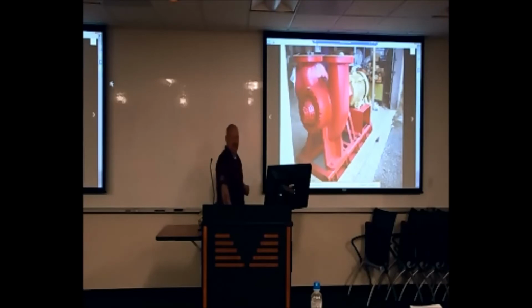You hear that big loud bang, then you know that you've probably got a big air problem in there. I would put a little Hoffman air vent up on the top of this unit, and it'll just automatically bleed off the air as it gets in there. That way when the pump goes to start up, there's not a big violent surge of air going through there, and then water, and a big bang to go along with it. And those check valves really don't like that either, because they'll see a bit of air and slam open, slam close, and that's usually the big bang you're hearing.